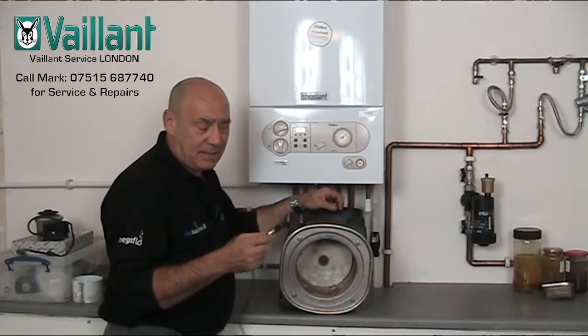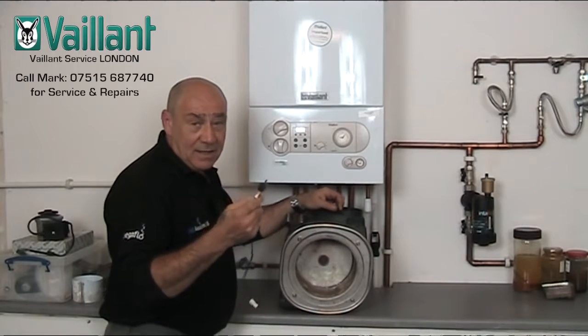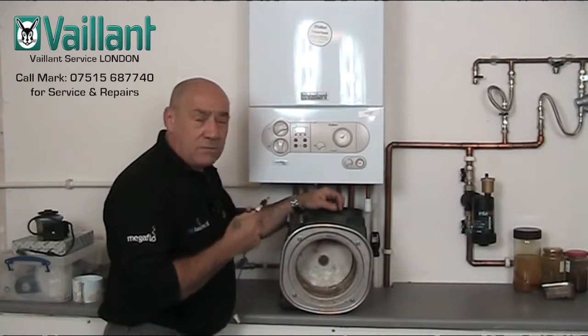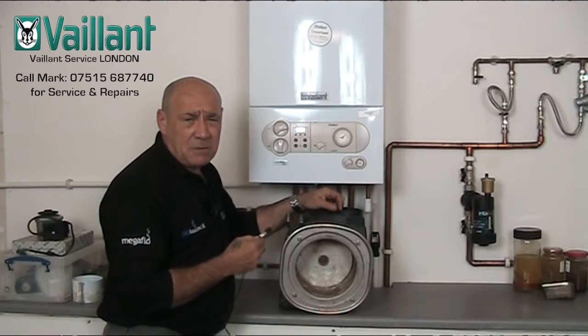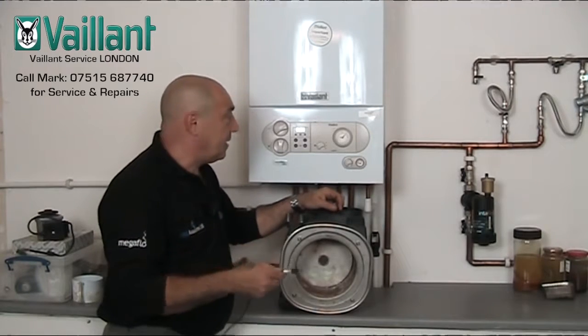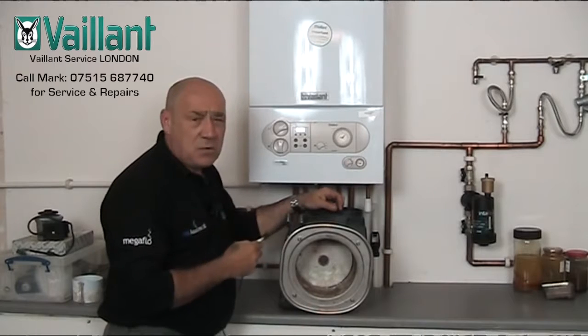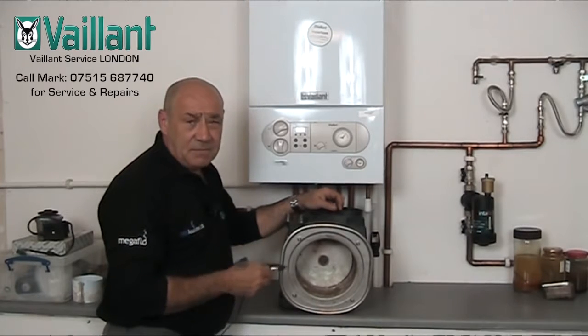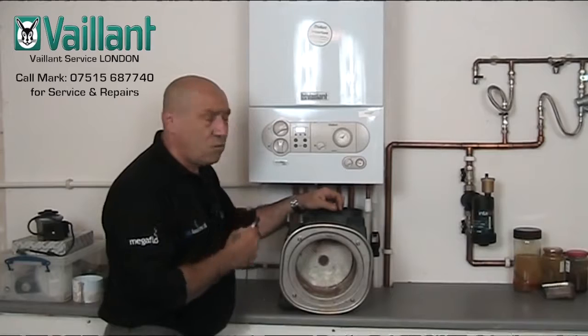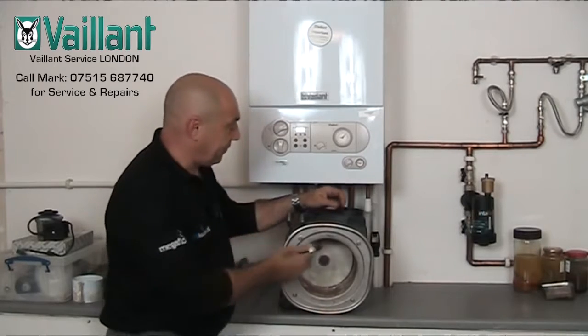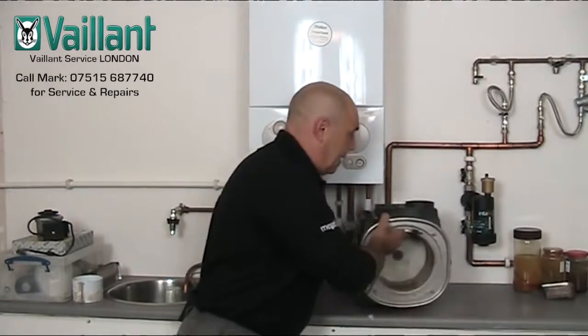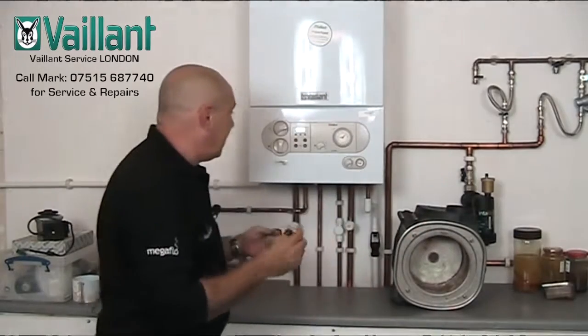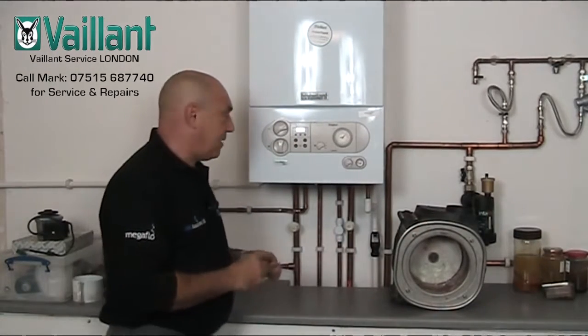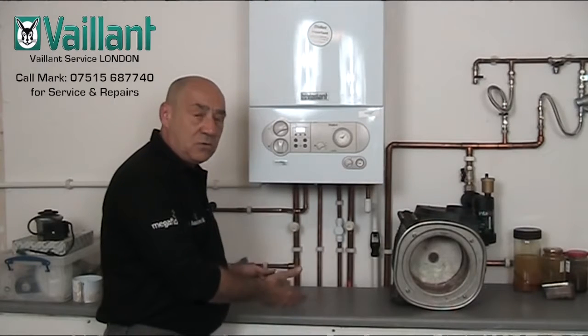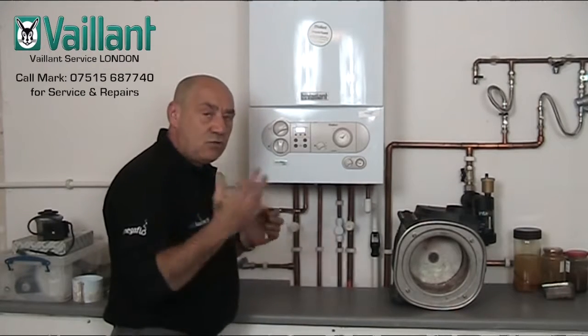Now, I cannot believe the amount of engineers and plumbers out there that don't even know what this is, they don't know what it does, and they don't even bother reading the book to find out what the P0 test program is. And when I worked for Vaillant, on many occasions, brand new boilers have been completely wrecked because the plumbers had turned the boiler on before running the test program. So, just quickly, I might as well show you while we're here. This is how you run a P0 test program, and every time you drain a boiler or empty the boiler of water or fill it back up again, you should run this test program.